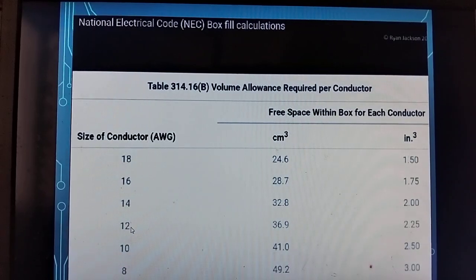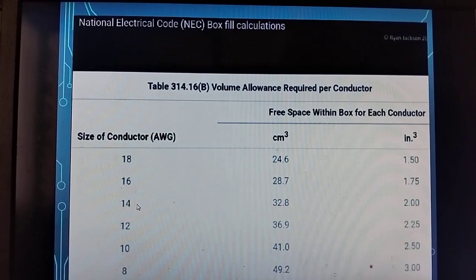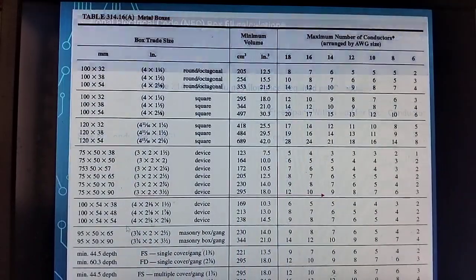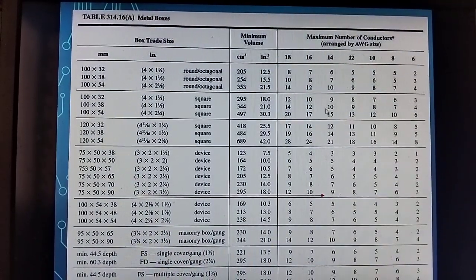Let's say in one junction box you put 12 conductors. You multiply this by 2 cubic inches, so you can get the volume allowance. Let's see, like this.